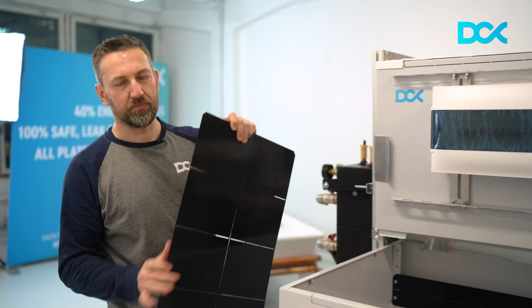It may happen that you will start with just a small amount of miners, let's say for the first trials, 4 of them, 6 of them, 8 of them, and thus for that part of the enclosure which is not occupied by the miners, you should use that plate, put it on the bottom to force the fluid to go through the miners only.